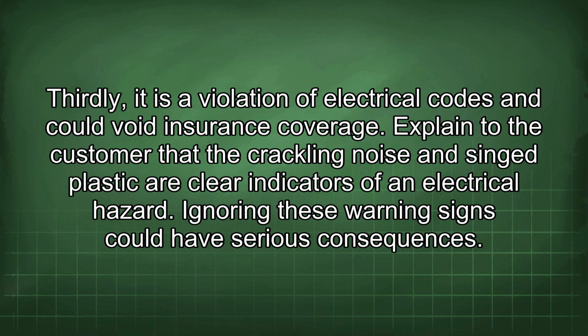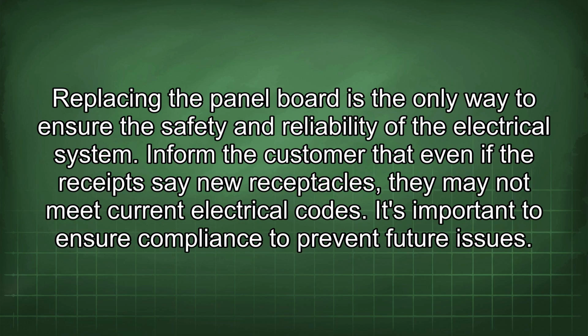Explain to the customer that the crackling noise and singed plastic are clear indicators of an electrical hazard. Ignoring these warning signs could have serious consequences. Replacing the panel board is the only way to ensure the safety and reliability of the electrical system. Inform the customer that even if the receipts say new receptacles, they may not meet current electrical codes. It's important to ensure compliance to prevent future issues.